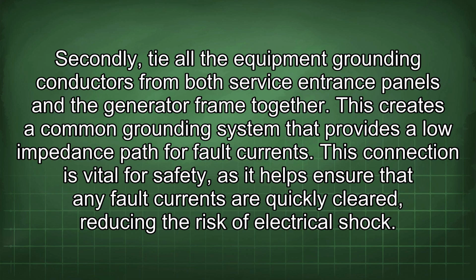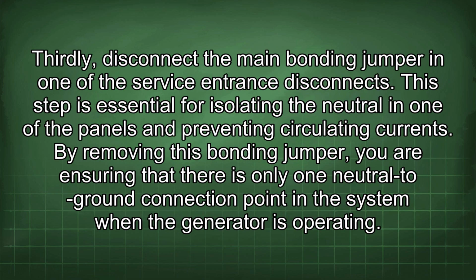of electrical shock. Thirdly, disconnect the main bonding jumper in one of the service entrance disconnects. This step is essential for isolating the neutral in one of the panels and preventing circulating currents. By removing this bonding jumper, you are ensuring that there is only one neutral to ground connection point in the system when the generator is operating.